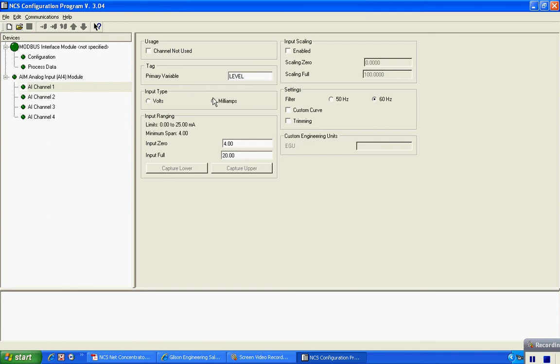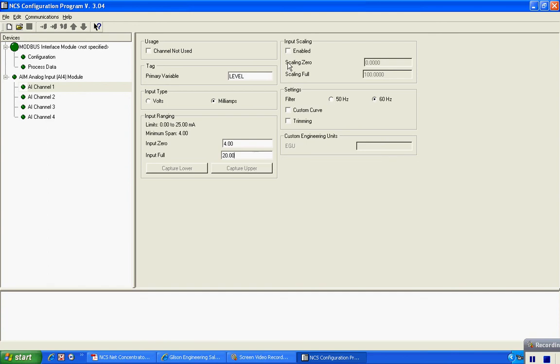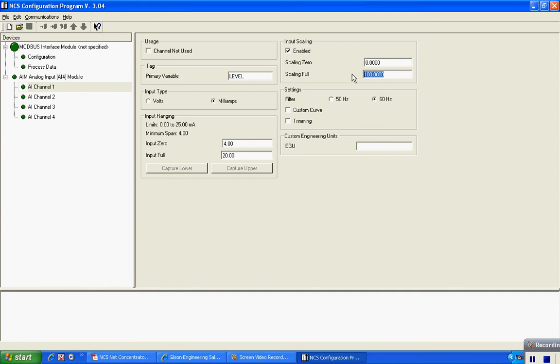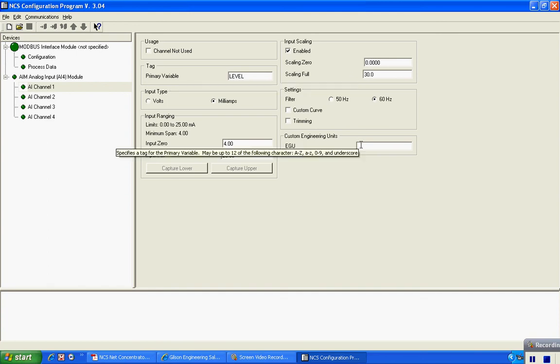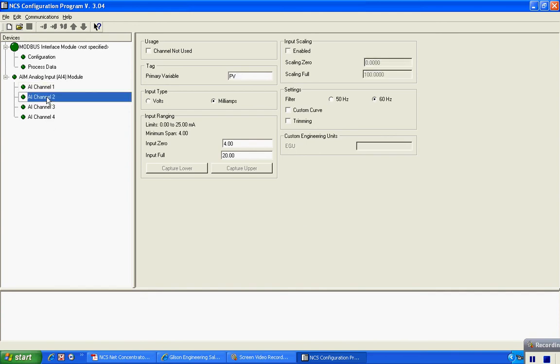I can configure this with a primary variable name and I'm going to call this a level input signal. I have a 4 to 20 level transmitter out there so I'll leave this at milliamp. I have a 4 to 20 milliamp signal coming in and I need to input my scaling numbers here because I'm going to read a signal that's 0 to 30 feet. So at this point I put 0, 30 feet, and I'll put my engineering units down here, and I've configured my first input.